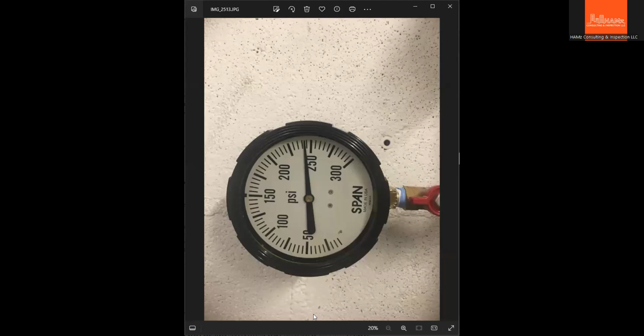So bear in mind this is 240 or 245 psi pressure for chill water. And a side step on our testing observation, this is also part of the job. The contractor, I think, asked me if this ductwork penetration needs to be protected, because it's a new duct and an existing wall. So as per code, they need to restore the previous rating of the wall. If this is a fire rated wall, you need to have fire caulking around the ductwork. So this gap is unacceptable, and those penetrations need to be patched up.